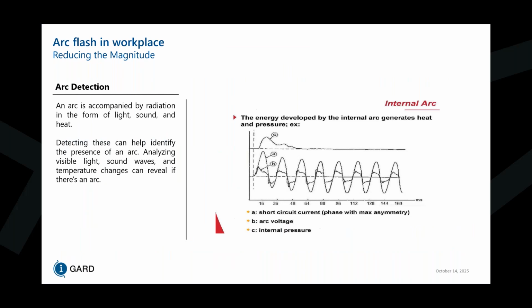An arc is accompanied by radiation in the form of light, sound, and heat. Detecting these can help identify the presence of an arc. Analyzing visible light, sound waves, and temperature changes can reveal if there's an arc. So even pressure sensors are also viable in this situation to determine if there's an arc in the system. However, the pressure sensors are not as fast as the light sensors. The light sensors are pretty fast, between 1 to 10 milliseconds, depending on how fast your switching scheme is at your breaker. Usually there's 5 cycles, but I've seen that there's some 3-cycle breakers as well.